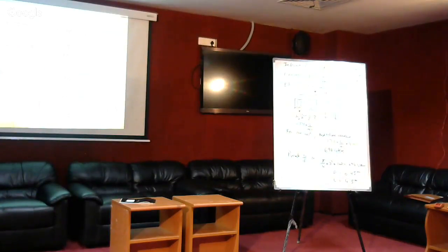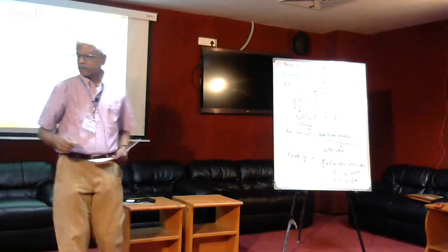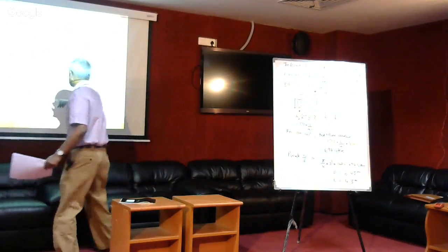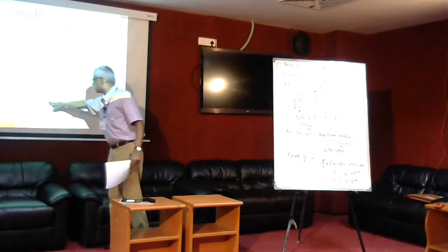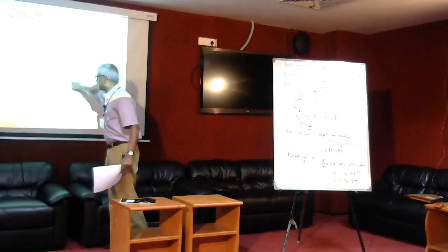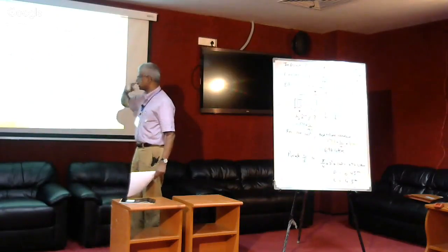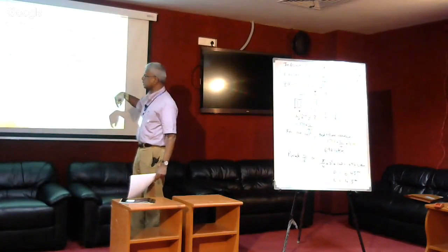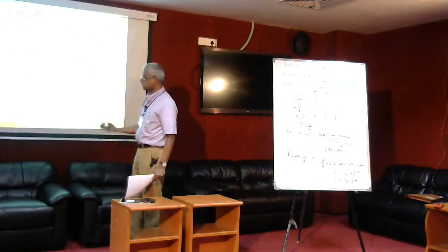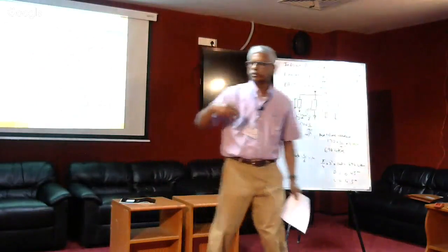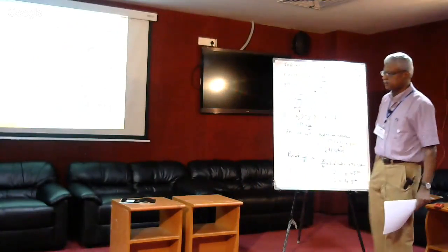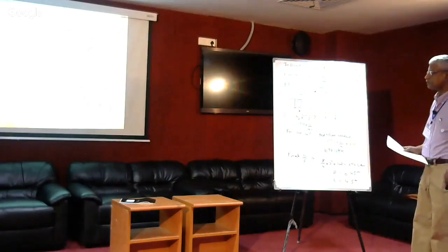Now, in practice, what we do is when it reaches this breakthrough, we then put it onto another column. And so even after this breakthrough, when the phosphorus concentration is increasing, since it is going to the other column, at the end of the second column, you will get again non-detect. So that's how we use most of the column volume or mass.